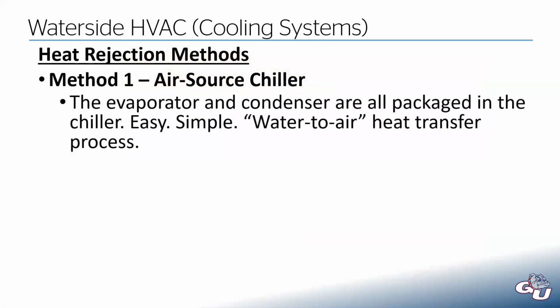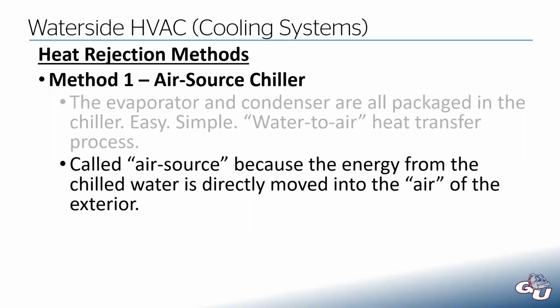With an air source chiller, the evaporator and the condenser, it's all packaged into the chiller. When we were talking about heat pumps and air conditioners before, we talked about how you usually have an indoor unit and an outdoor unit, and they're piped together. In an air source chiller, this is all packaged in that box we were just looking at. And this would be a water to air heat transfer process. The reason they call it an air source chiller is because we're taking energy from the chilled water and putting that directly into the outside air, just the ambient air of the building. So the outside air is our heat sink. That's where we are rejecting the heat. So that's where this term air source chiller comes from.